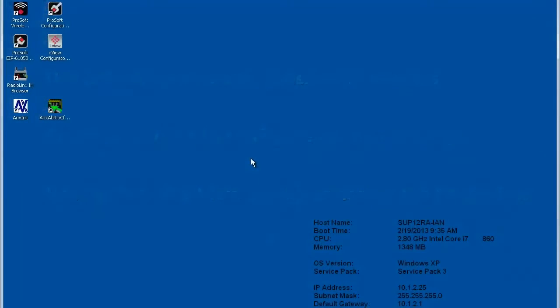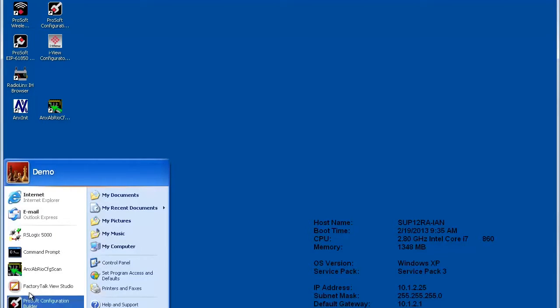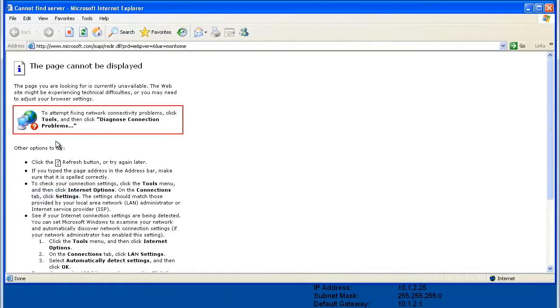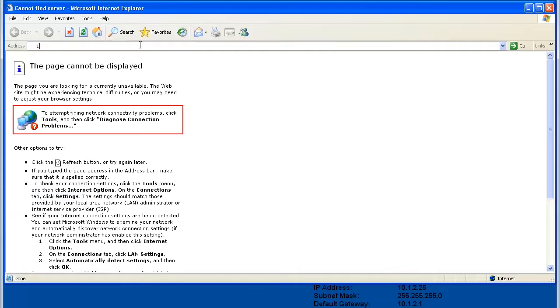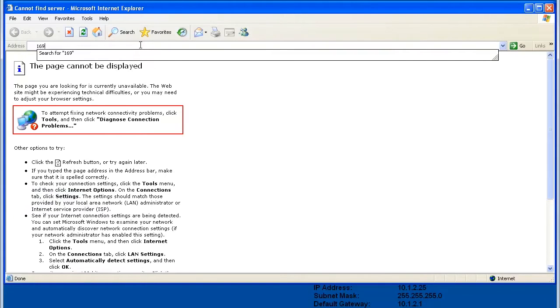To get started, I'll access the ANX2's onboard web interface where I can change the IP address and assign a new hostname. The ANX2 gateway is shipped with the link-local IP address of 169.254.42.84, which can be accessed regardless of what subnet your computer is using.